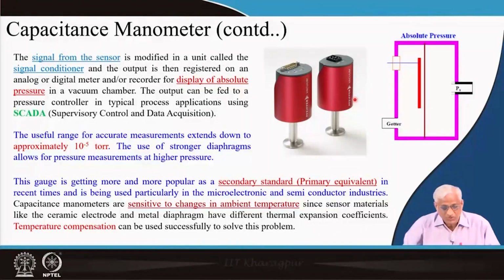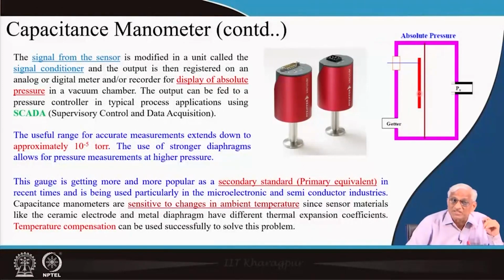So this is an absolute pressure measurement with differential pressure, one side being 0 and sealed off, and capacitance will be converted into frequency. Why frequency? Because frequency is one thing which can be measured to 1 in 10 power 8, 10 power 9, using the super heterodyne principle, etc., at gigahertz, for example microwave frequency.